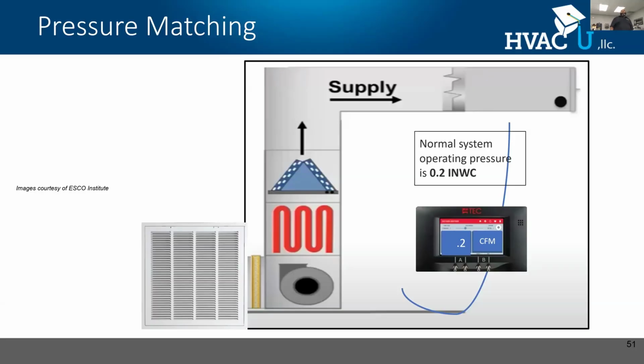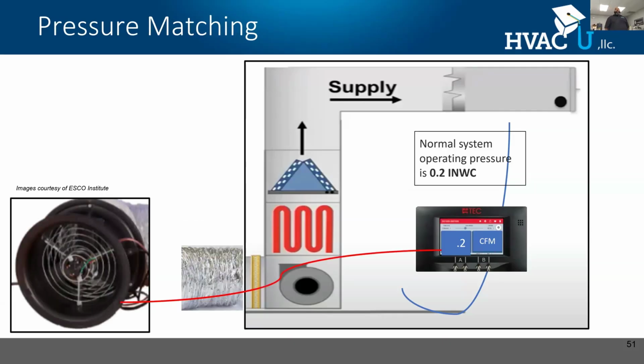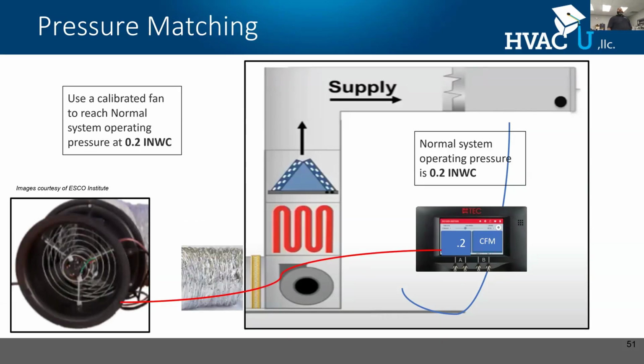Let's talk about pressure matching. Pressure matching is a way to get system airflow. How it works, I'm going to take a duct leakage tester. First I'm going to run the system and get a pressure measurement in the duct system, and my manometer is going to save that pressure measurement. Then I'm going to turn the system off and run my duct leakage tester. My duct leakage tester is going to increase in flow until it matches the pressure. When it matches the pressure, it tells me how many CFM it took to get through the duct system to match that pressure. So it's a neat way to get a system airflow by using a duct leakage tester.